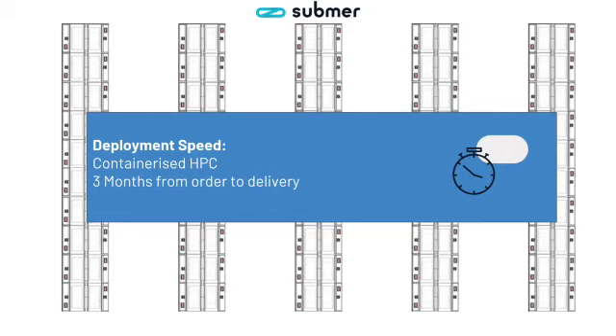So it's usually closer to other people working, and they complain about the noise, and then the air is not filtered, so they just take a normal air conditioning unit, the one that you would use in an office, and they crank it up to 11, and they pretend that's good enough to cool these machines. So the machines are getting dirty air, they're not getting cooled properly. So also in those cases, I think a completely sealed container with immersion cooled servers would be of much more advantage, and would provide more comfort also to the people that are going to sit around this reclaimed space.